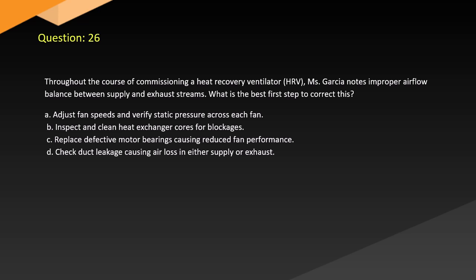Question 26. Throughout the course of commissioning a heat recovery ventilator, Garcia notes improper airflow balance between supply and exhaust streams. What is the best first step to correct this? A. Adjust fan speeds and verify static pressure across each fan. B. Inspect and clean heat exchanger cores for blockages. C. Replace defective motor bearings causing reduced fan performance. D. Check duct leakage causing air loss in either supply or exhaust.